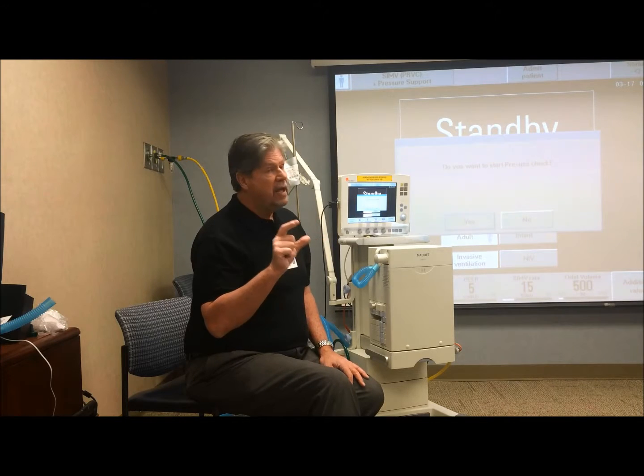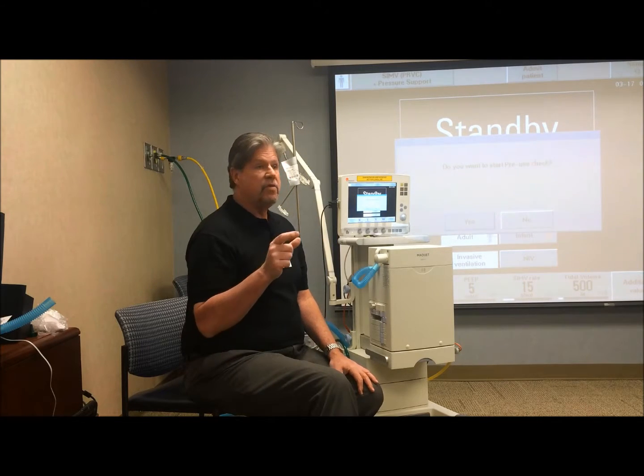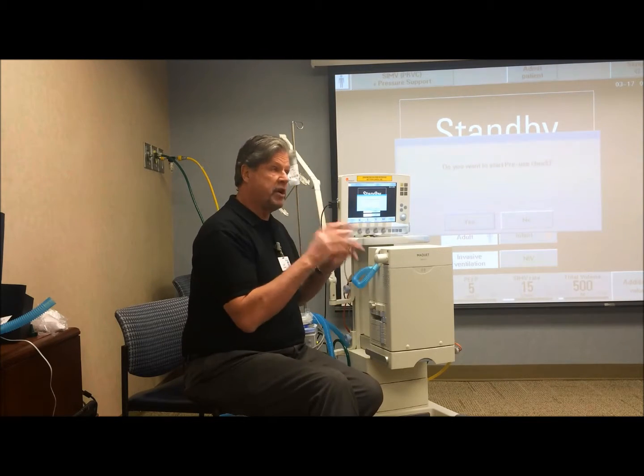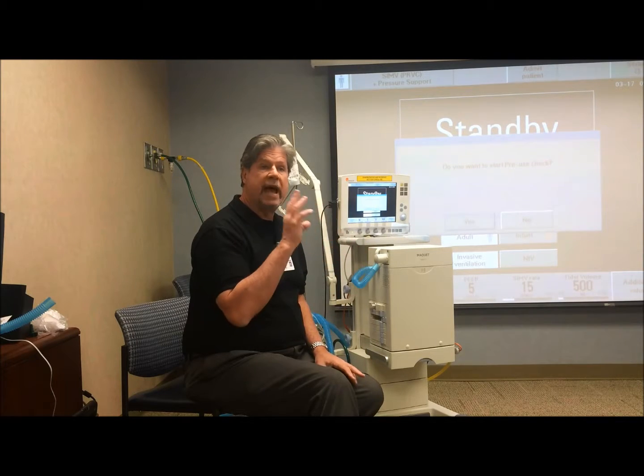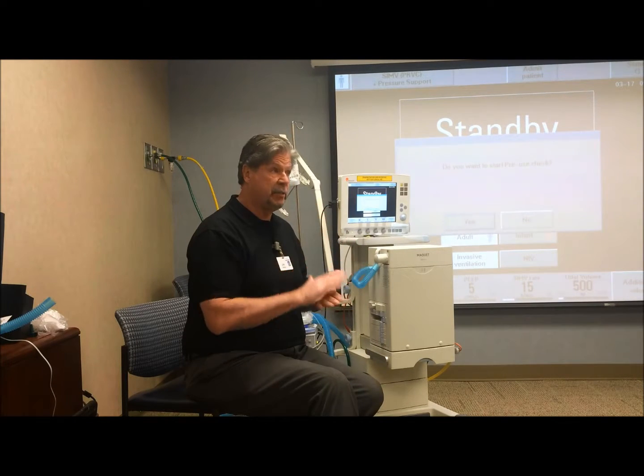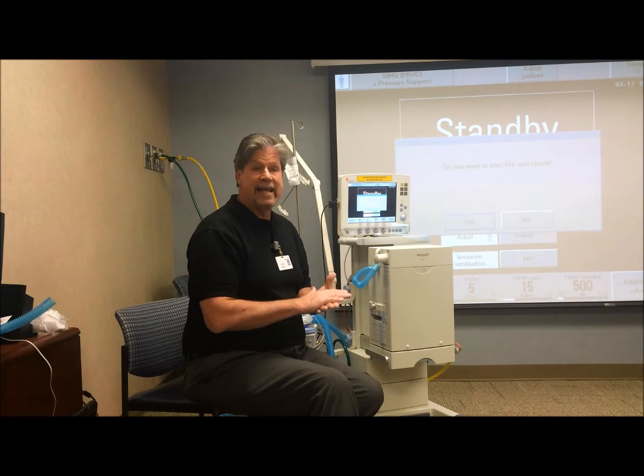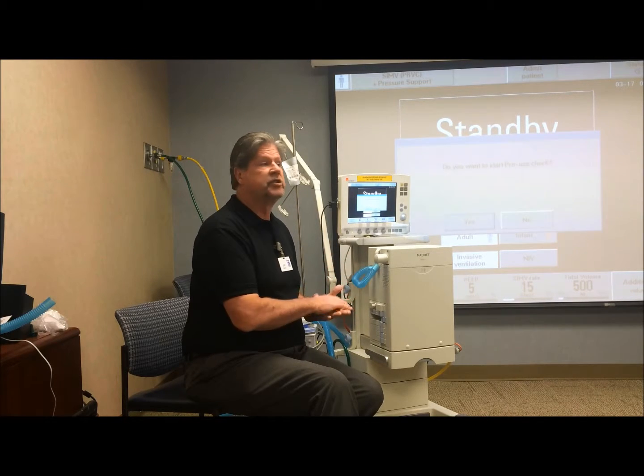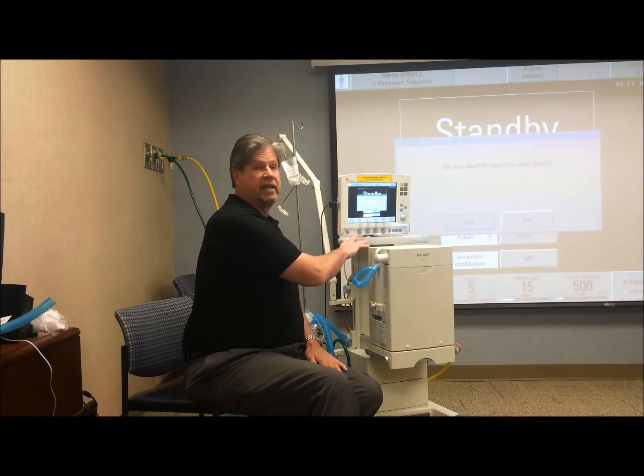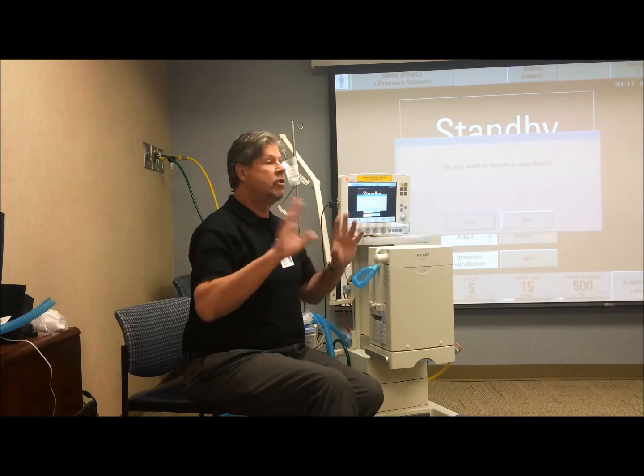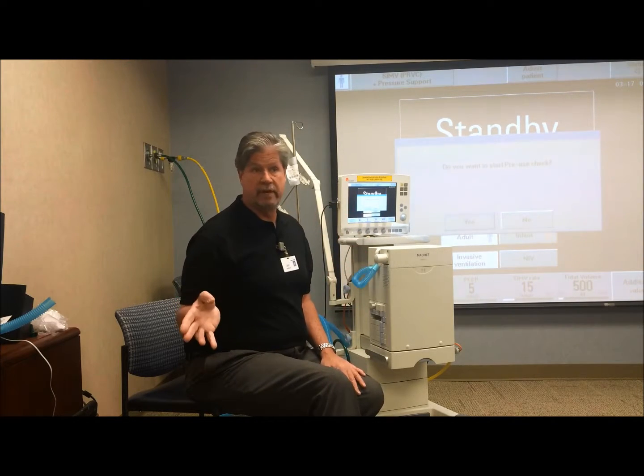on a patient. Now that means then if you DC'd the ventilator today and brought it into your equipment room, wiped it down, and put a new circuit on it and did the pre-use check now, that is before you put it on the patient. So in 3 weeks, when you have to set this ventilator up on a patient, you don't have to do the pre-use check again. It's already been done.